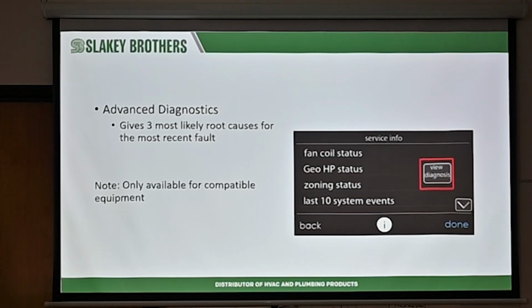high pressure trip, outdoor high pressure trip. Maybe those two go hand in hand because it tripped a high pressure because we don't have enough airflow through the indoor coil in the heat pump. But this is where you're going to find your last 10 system events. It ain't a whole history, but usually if something just recently happened a day or two ago, you're most likely going to see it there.